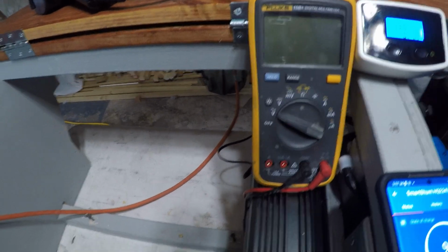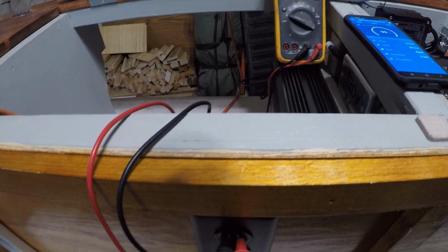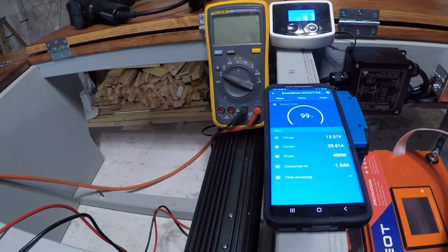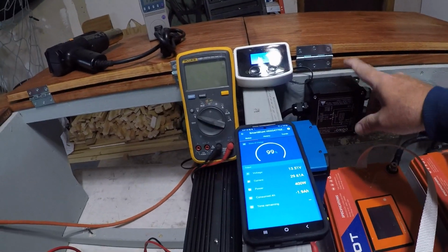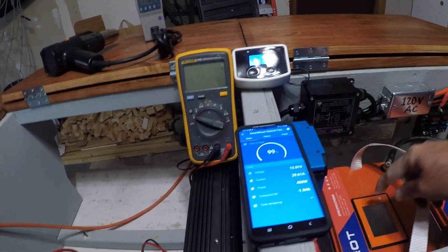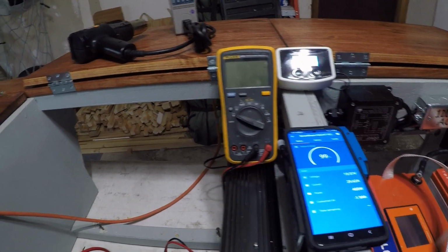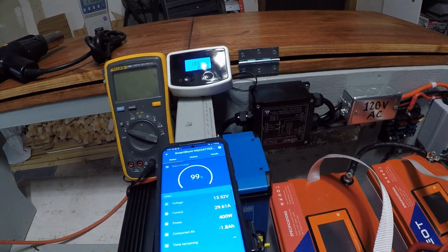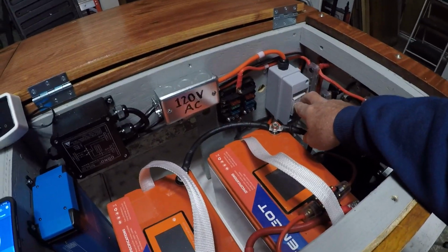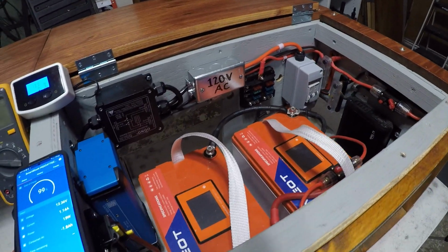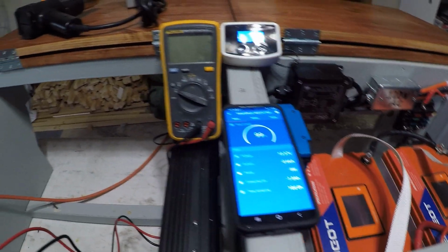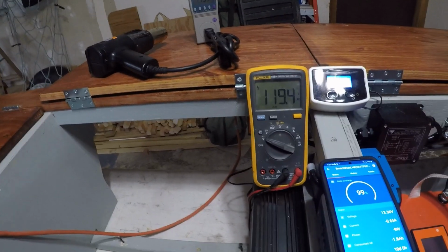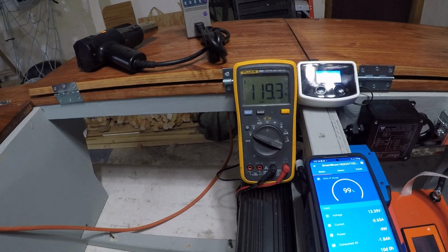It's showing 13.5 volts, but 0 volts out. Reason being, we still have power available to the switch here, so it hasn't switched over to the batteries yet to provide power for outgoing stuff. So if I turn off the circuit breaker and suddenly we're without that power... ta-da, 120 volts again. Now we're completely on the batteries.